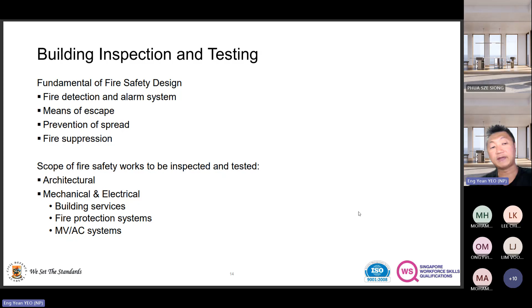ACMV, MVAC - same thing. ACMV is your air conditioning system, the AHU, providing air into the tenanted space. Should there be any fire, we definitely need to cut off the air supply so the AHU stops running. Once the return detects smoke in the tenanted unit, meaning there's a fire, I need to stop all the air supply - by removing oxygen and not providing any, we're able to control the fire from spreading.